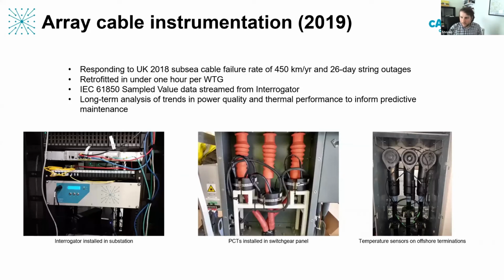Okay, so this is slightly out of order, but this is our first installation at the OREC facility at the east coast of Scotland. So you see on the left is our central interrogator unit, which is just installed in an IT cabinet in the onshore substation. In the center, you can see our passive CTs installed there. I know it's a bit confusing to see what's connected to what there, but the only thing they're connected to is an optical fiber.